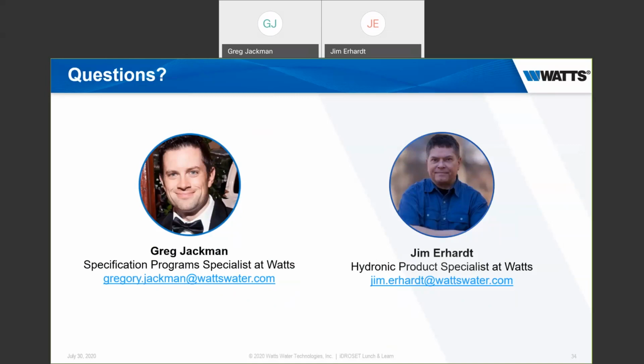In that regard, you can orient the iDROSET any way you want in relation to the axis of the actual line it's installed in. Okay, if the gauge fails, is it replaceable, or do you need to replace the entire unit? At this point, I am unaware of replacement parts. That gauge is really built into the valve. There's not a lot inside that gauge that can fail.